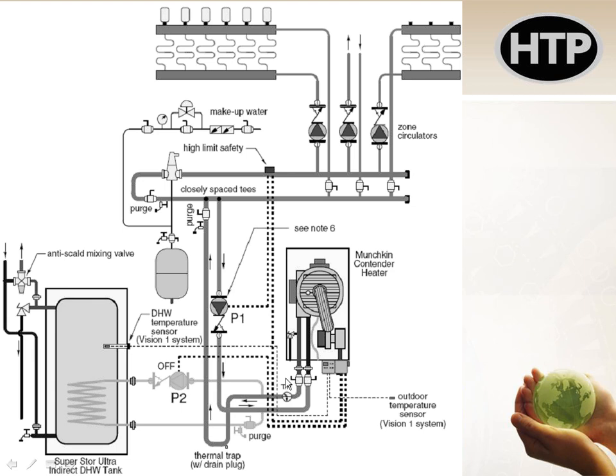Instead of having one big loop going throughout the building, I have two loops. One in the boiler room that's just circulating water through the boiler and moving heat from the boiler to the secondary loop and then back. And then I have a second loop that goes out and hits all the zones. So with these condensing boilers, these stainless steel heat exchangers from almost every manufacturer, you have to do primary, secondary piping. All right, so keep that in mind.